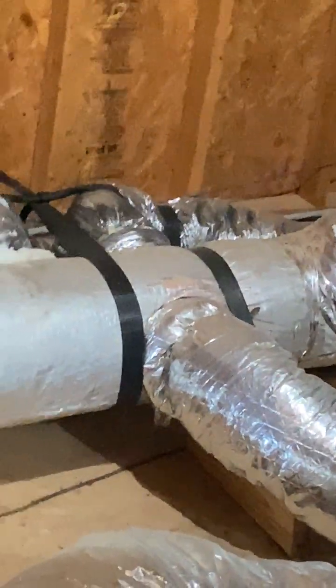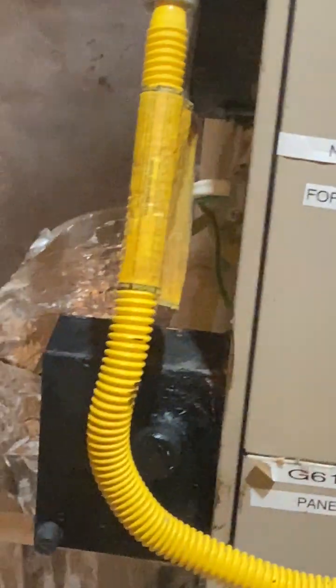And in the case of a small zone, you might be trying to push so much air that it creates a static pressure above your heating system. And what they do is they install a bypass, so air coming down here, some of it's simply bled off, and that's what that guy does. And what it normally does, it returns it back to the base here, and over here is a stub sticking out where there used to be this insulation. There used to be a bypass damper installed right down there, and when pressure got too high on it, it would open up and send that air back into the furnace unit.